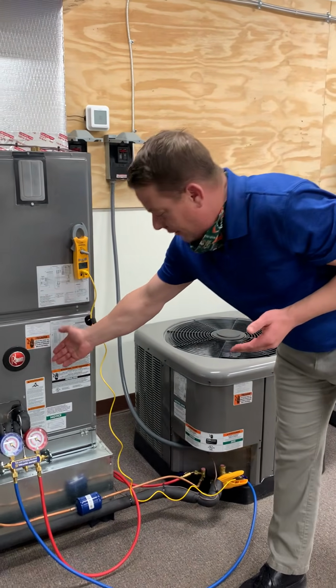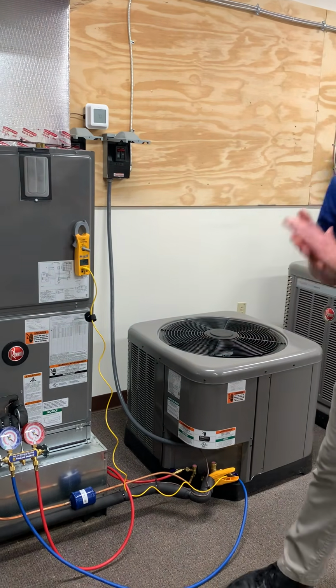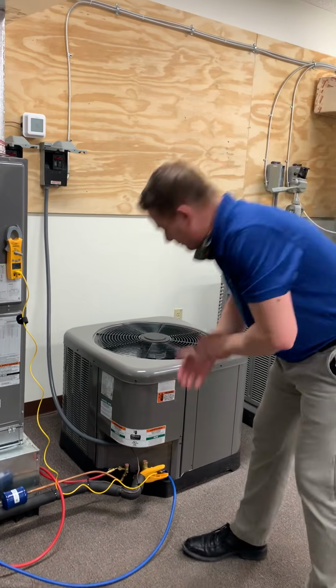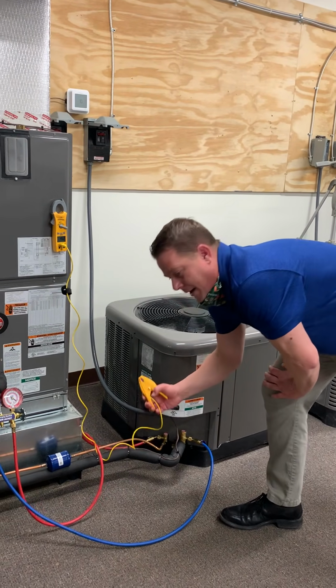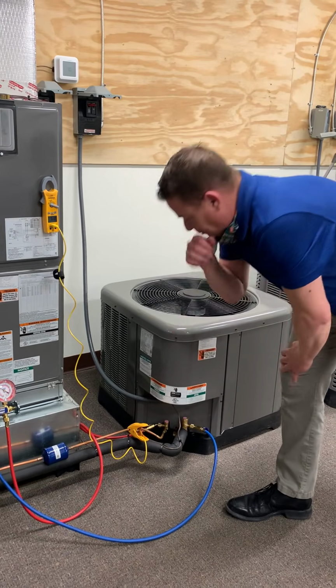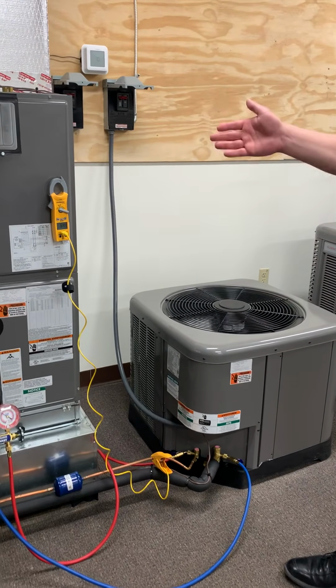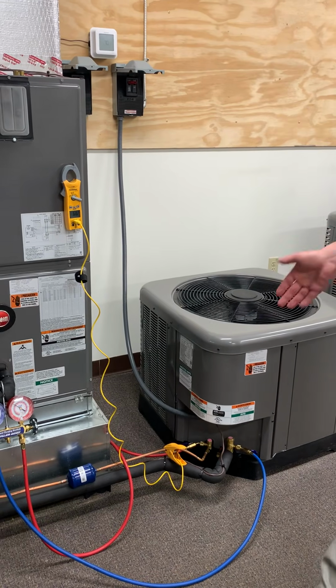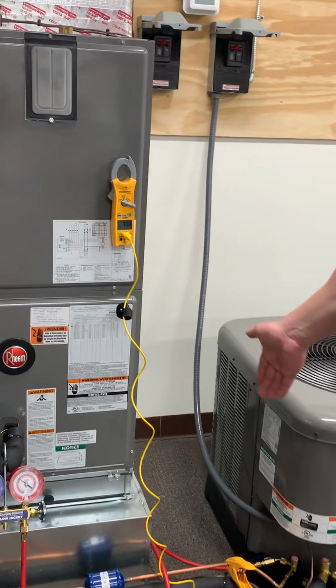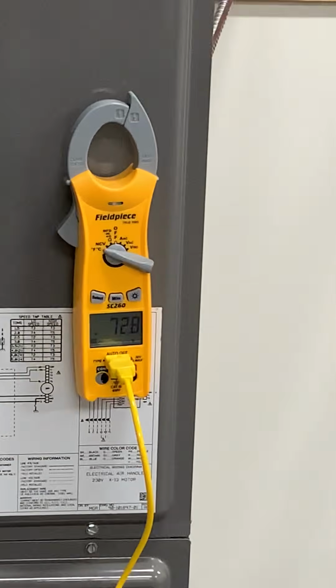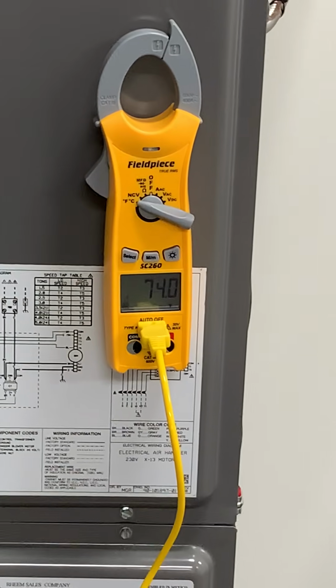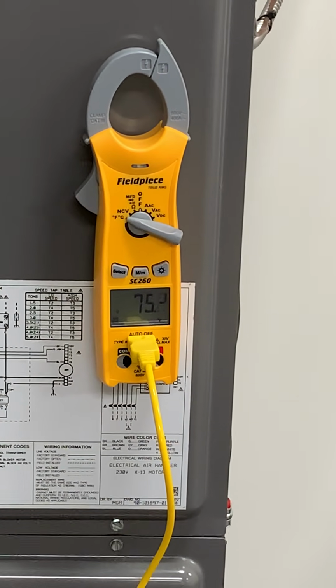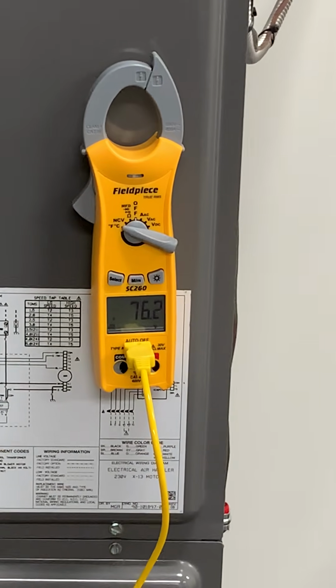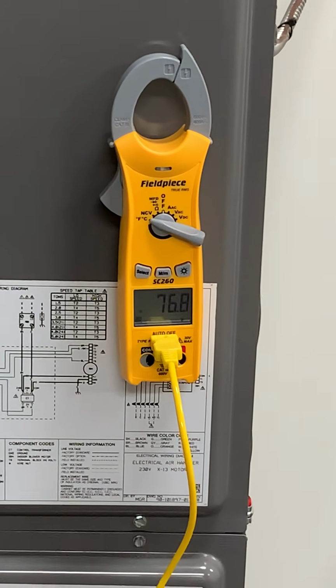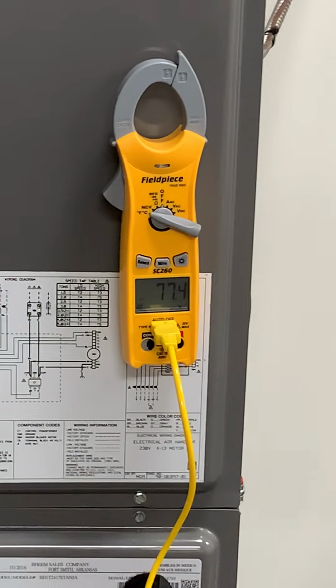This is an expansion valve system at the indoor evaporator coil. So I need to know my charge is right. I'm going to measure subcooling. I'm going to take my clamp-on probe, and I'm going to move it to the liquid line. Give this a second to stabilize and see where our temperature ends up. And you can see we're at about 74 degrees. We're still climbing a little bit. And we're at about 77 degrees.